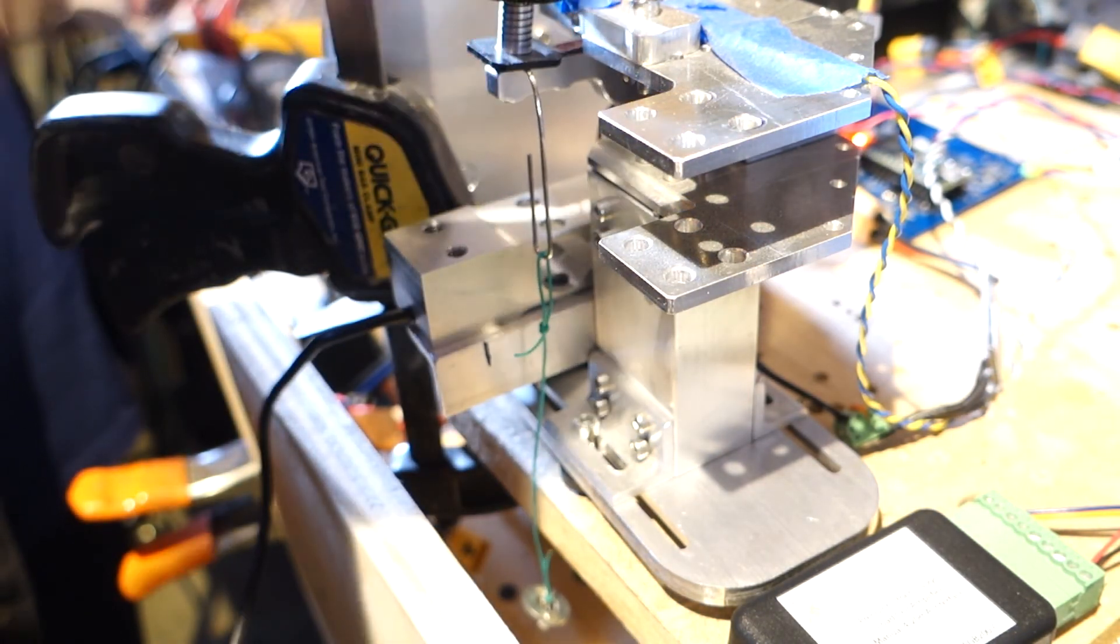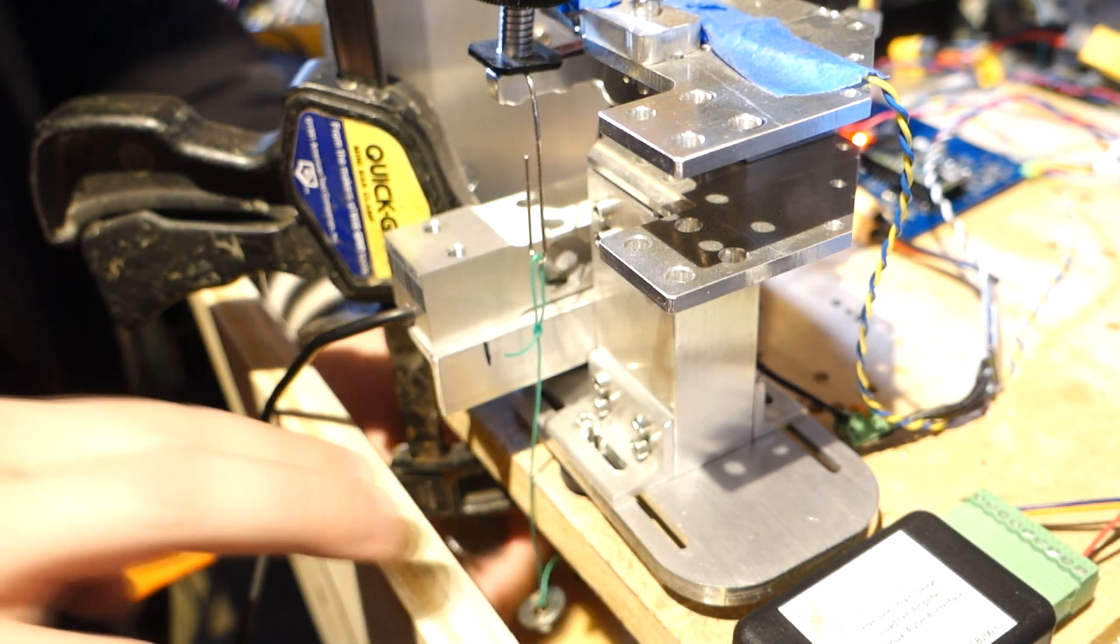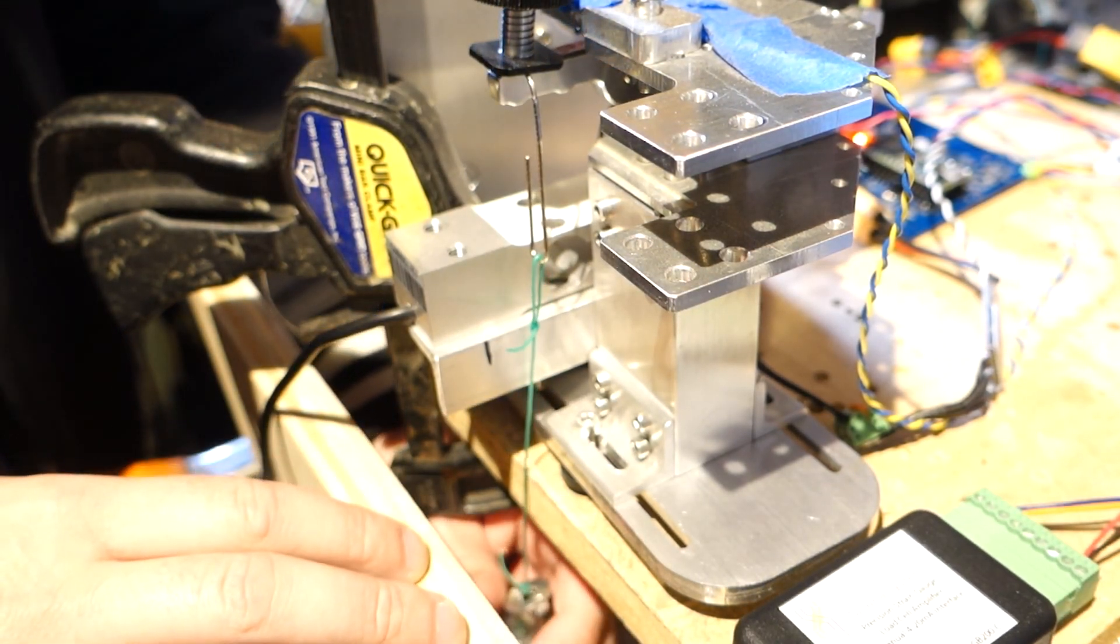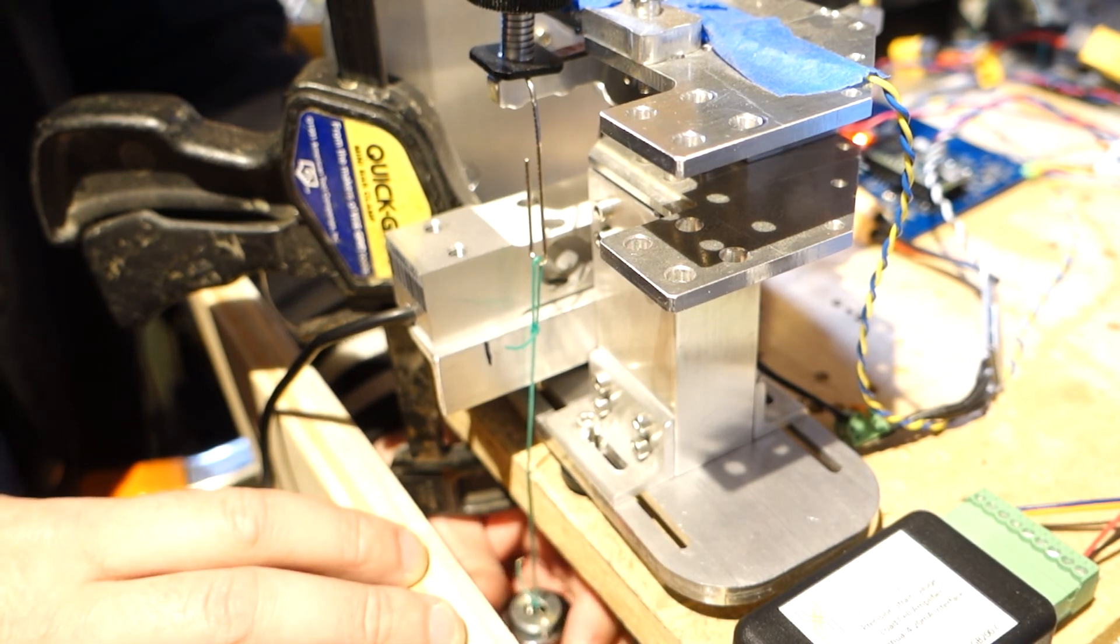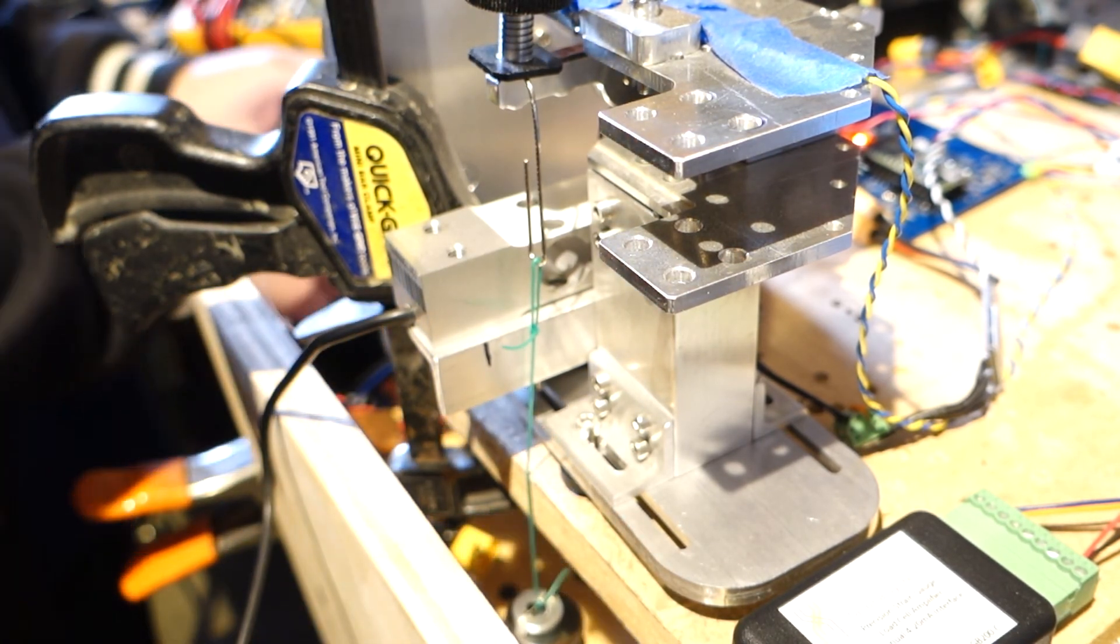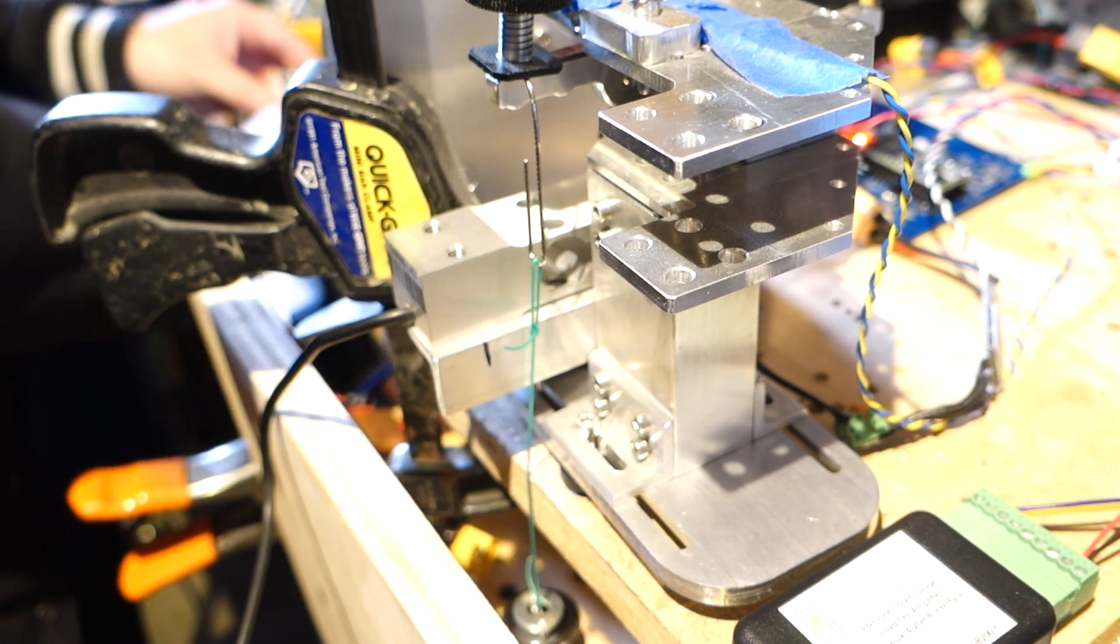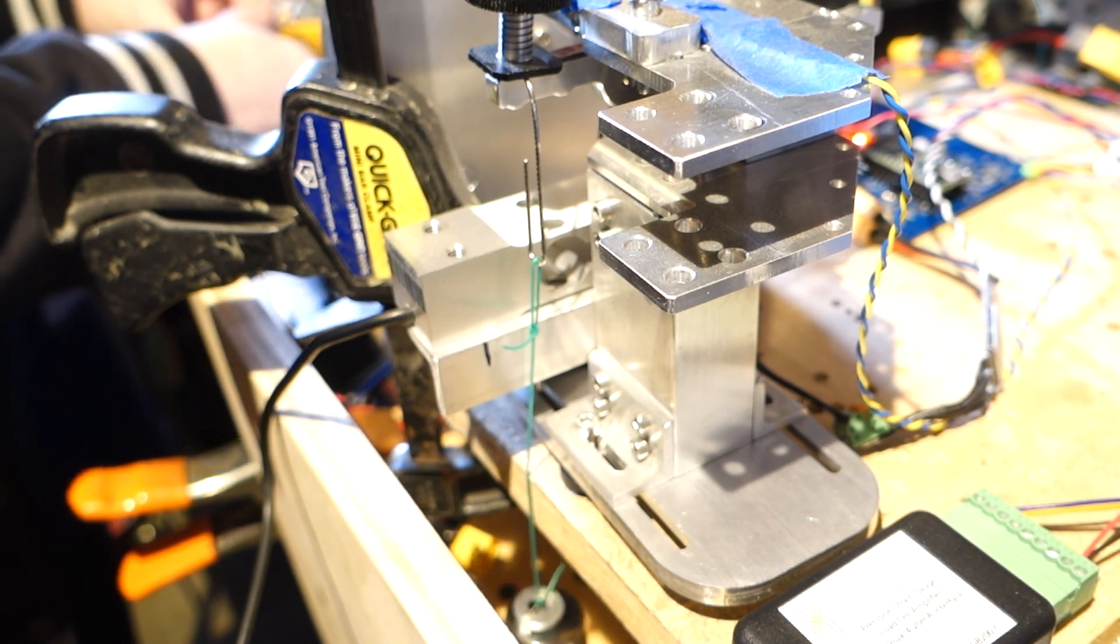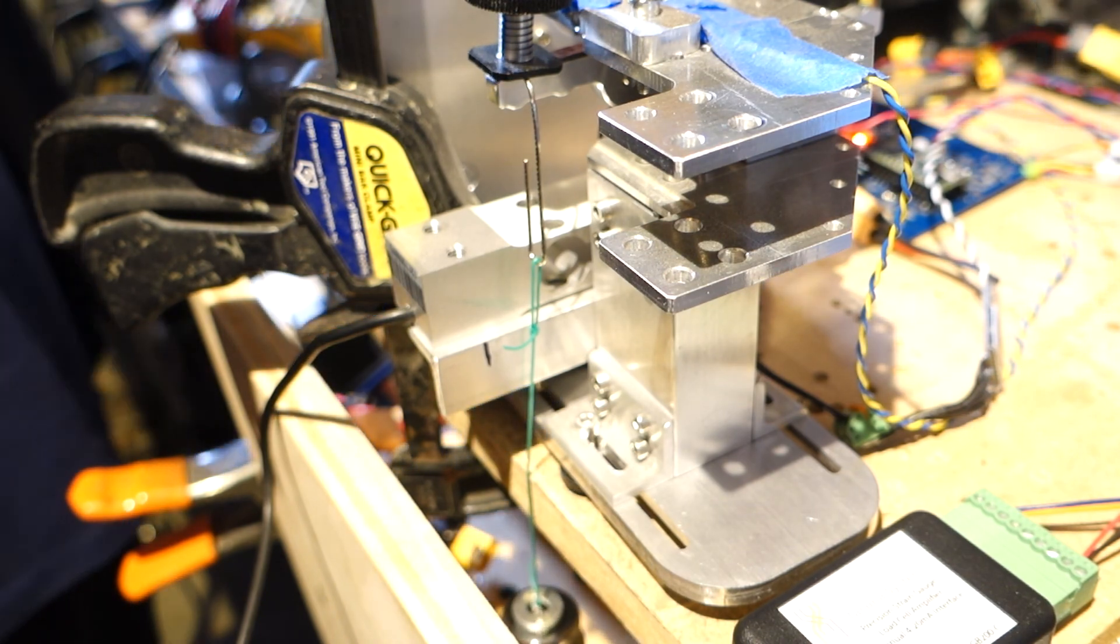I apply a little bit of extra weight to the torque arm just to preload it and take up any slop that might get in the way of the reading, and then apply the test weight to the magnetic end of the testing jig. Here I can grab the manually triggered samples or a fixed length test log just as with the voltage measurement.